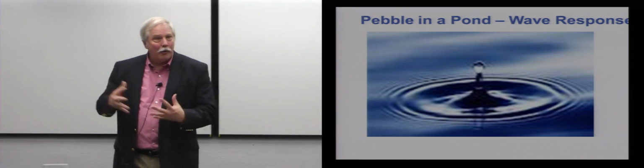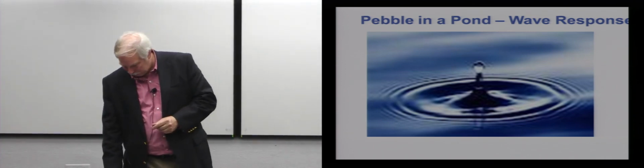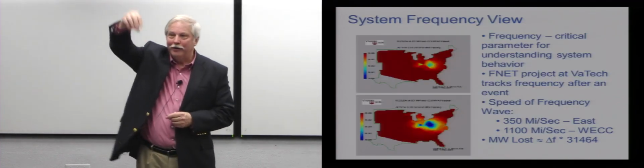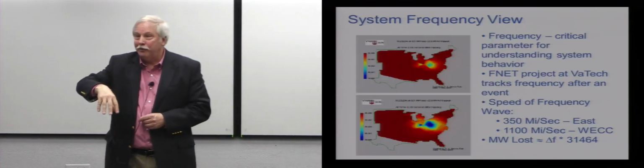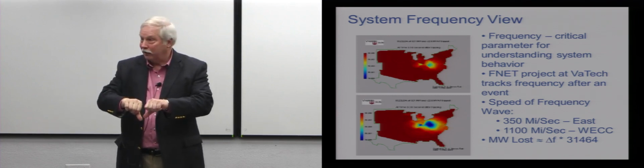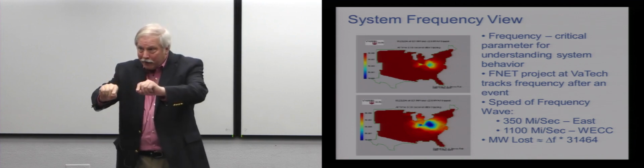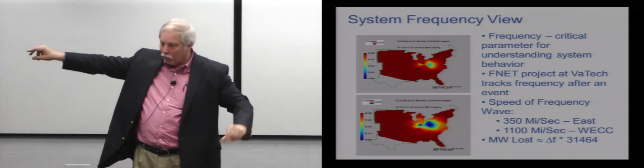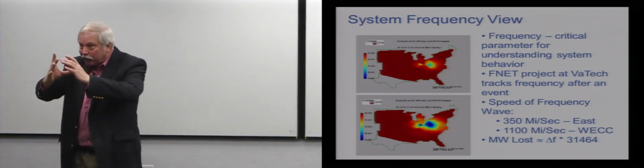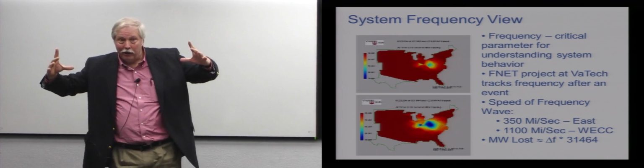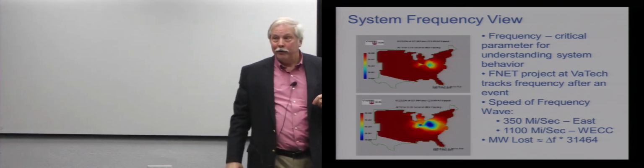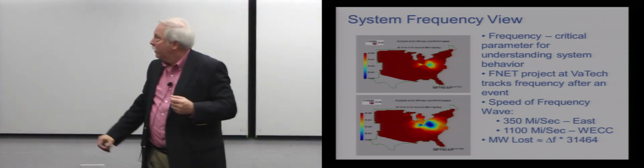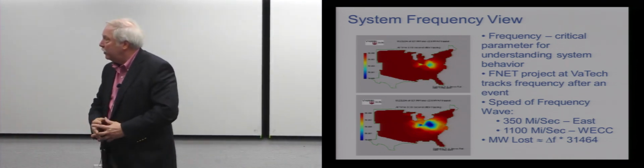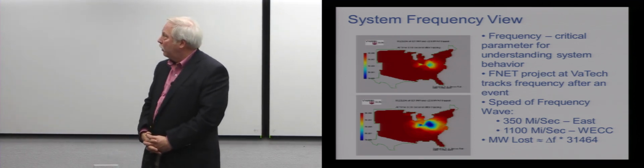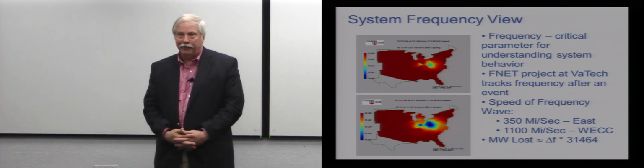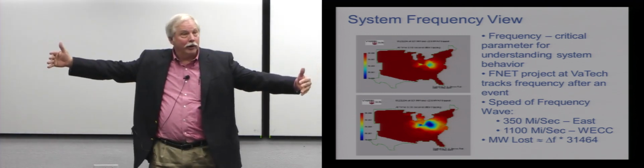Well, it turns out the power system is very viscous also. When you drop a power plant in the power grid, what happens to the frequency there? At that very center point, it's going to go to zero, of course, because the generator is going to trip offline. But it sends out a ripple of frequency. What you're looking at here on these diagrams is that ripple spreading out from the center of where the power plant went out. This frequency is a wave. On the East Coast, it travels at 350 miles per second. On the West Coast, it travels 1,100 miles per second. Why? Much longer lines with fewer interconnections and the like.